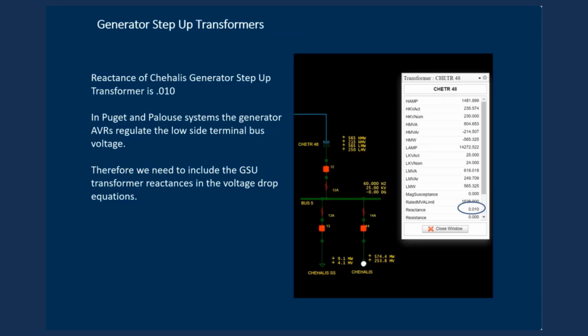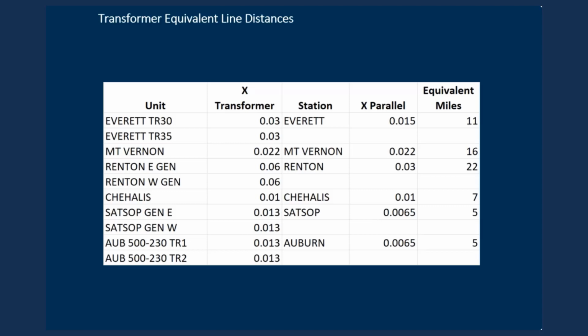Since we're regulating the low-side terminal buses, we have to include the generator step-up transformers in our calculations. We can find these values by clicking on the generator pop-up menu with the right mouse click. In this spreadsheet, we've gone through and we've calculated the equivalent miles for the different generator combinations throughout the Puget system. Where we have two generators in parallel, like at Everett, we take the impedance of each transformer and we combine it to an equivalent impedance, and then we divide that equivalent impedance by our 0.00135 impedance per mile for the 230 kV to get the equivalent miles. So for Everett, we have 11 miles for both generators in parallel.